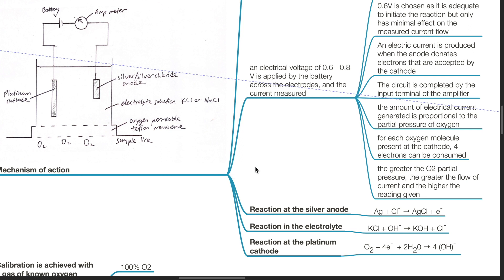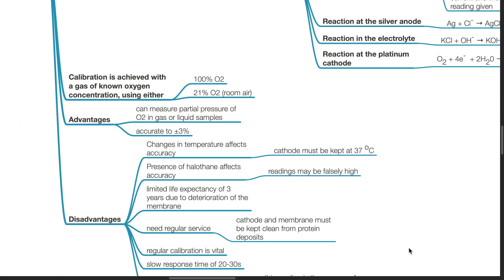Reaction at the silver anode: Ag + Cl⁻ → AgCl + e⁻. Reaction at the electrolyte: KCl + OH⁻ → KOH + Cl⁻. Calibration is achieved with a gas of known oxygen concentration, using either 100% oxygen or 21% oxygen (room air).